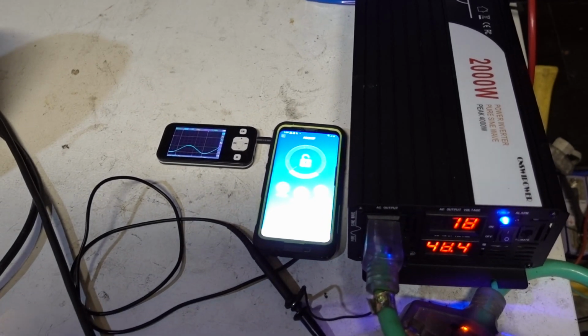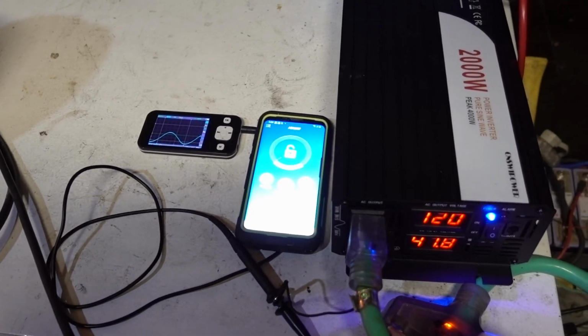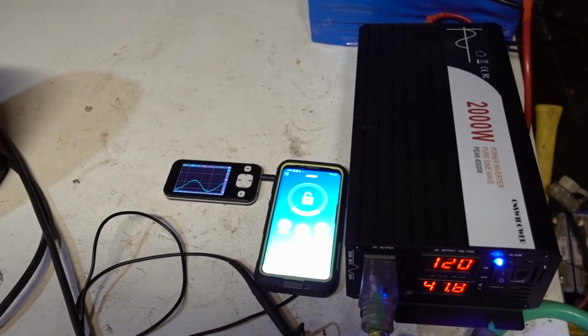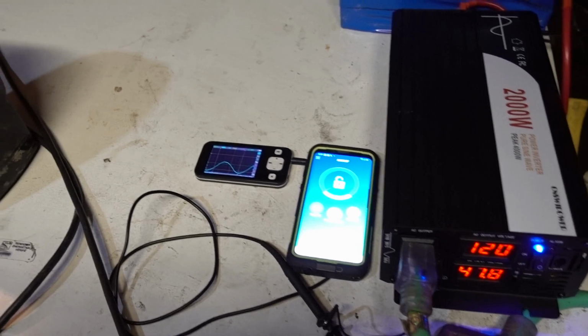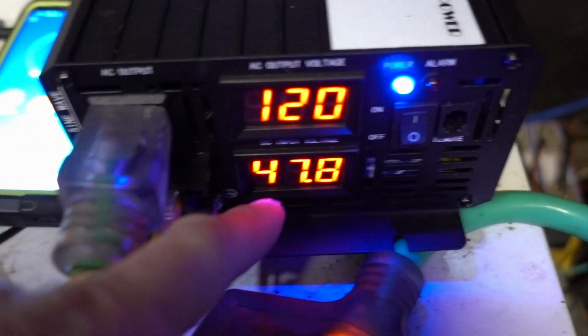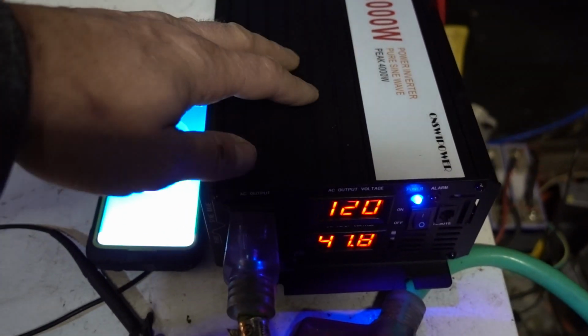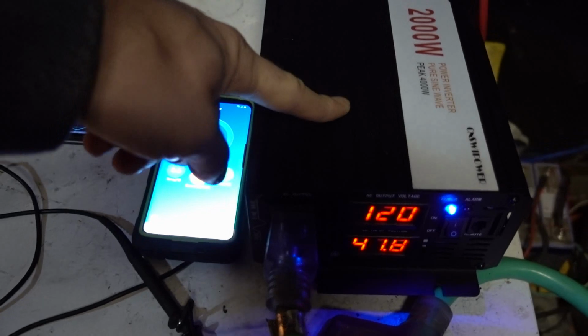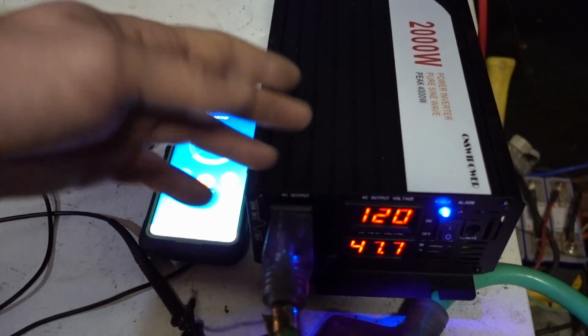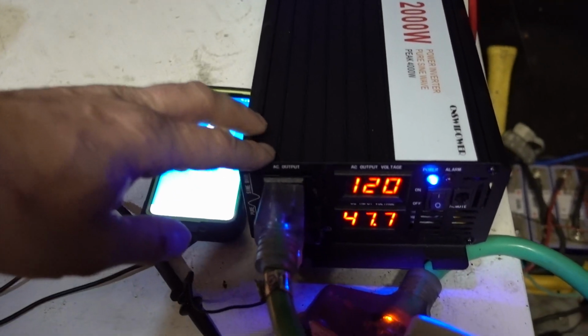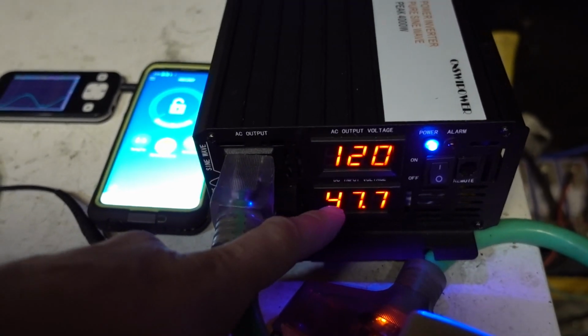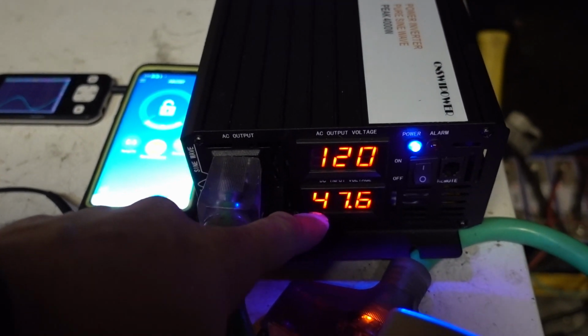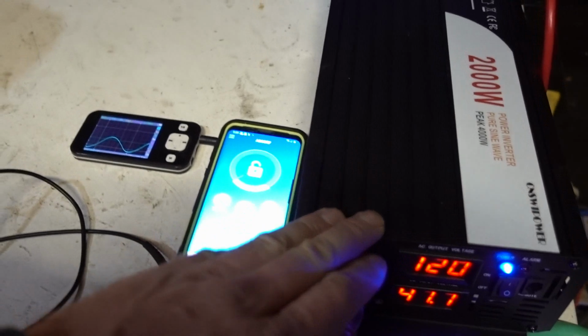I might actually really like this inverter. We'll see. And you got to remember, we are low - this is most likely designed for a 48 volt lead acid battery system, which would normally like to sit at a higher voltage, like 50-ish volts, especially on a large battery bank. But this is showing a very depleted battery. If this was lead acid, inverters have a hard time with that.